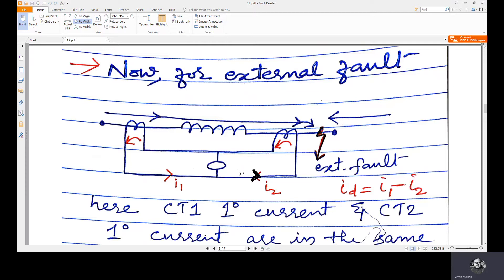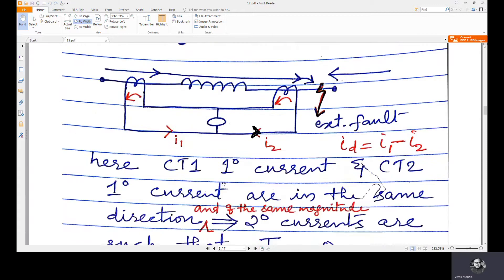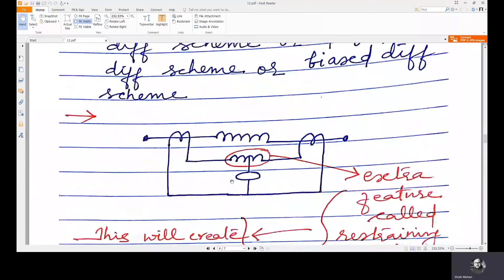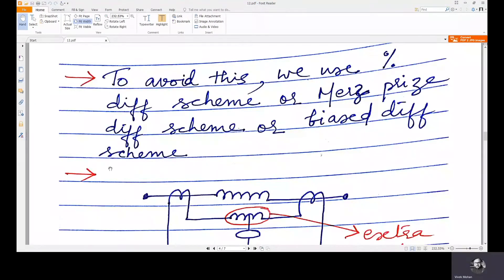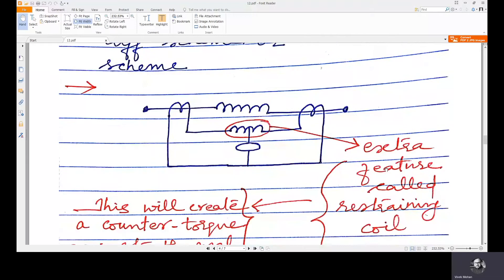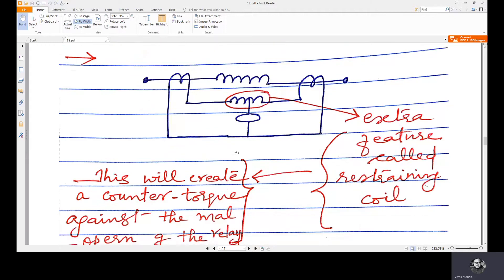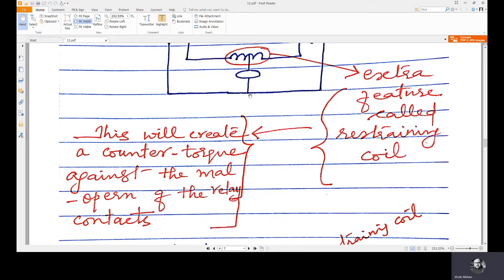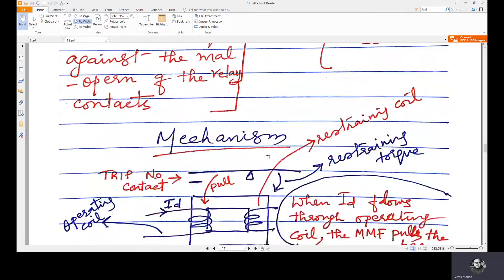To avoid this mal-operation, we can use a percentage differential scheme, also known as the Merz-Price differential scheme or biased differential scheme. Here we have introduced an extra feature: a restraining coil. The importance of the restraining coil is that it will create a counter-torque — a restraining torque — against the mal-operation of the relay.